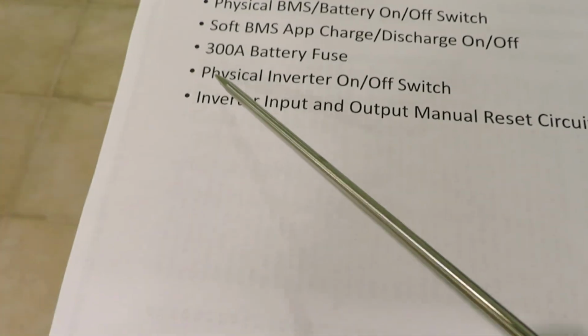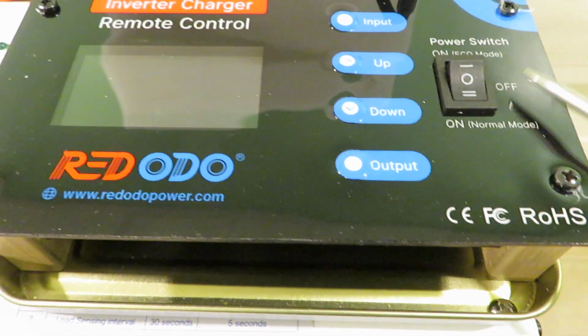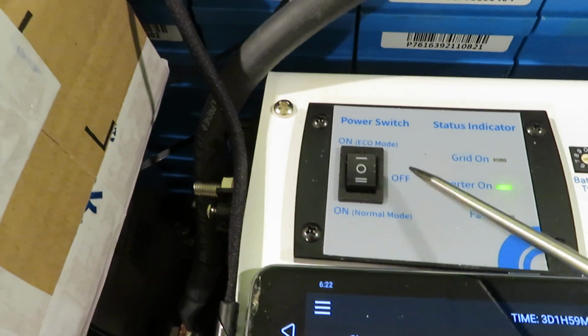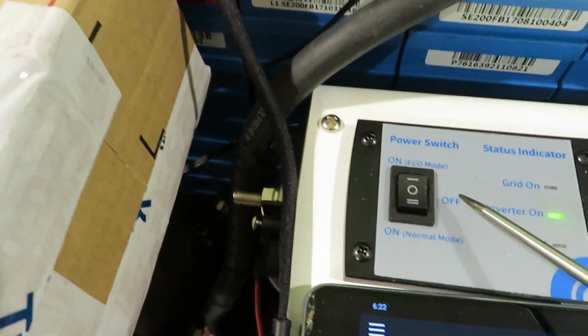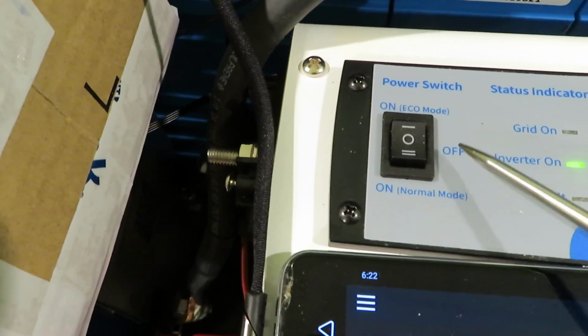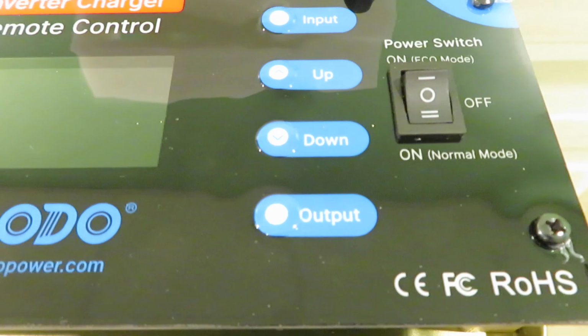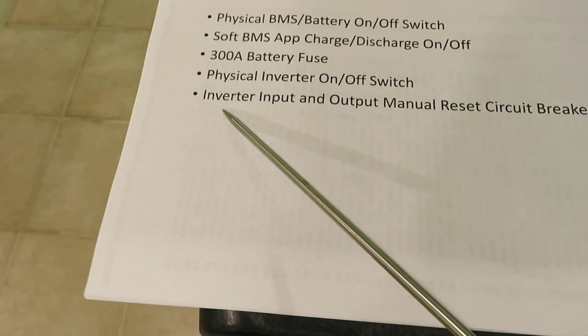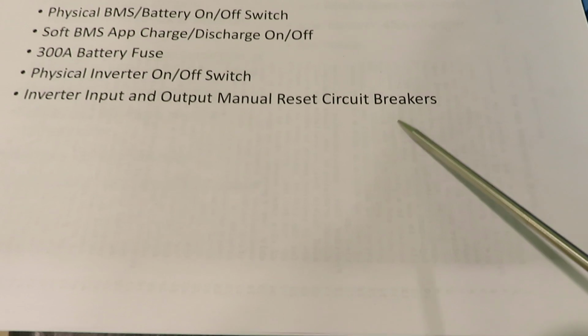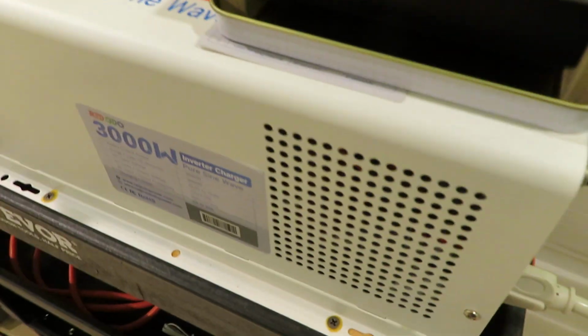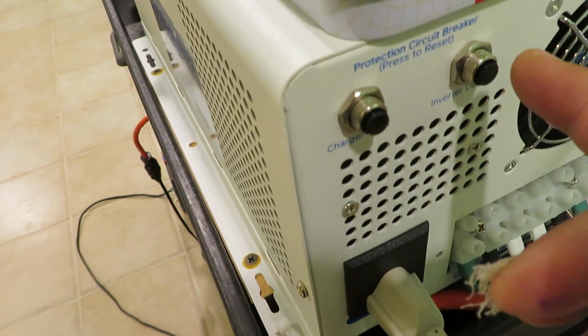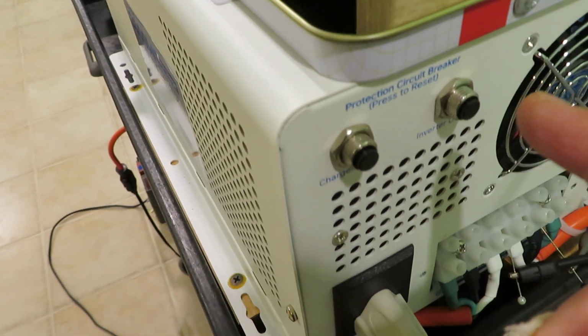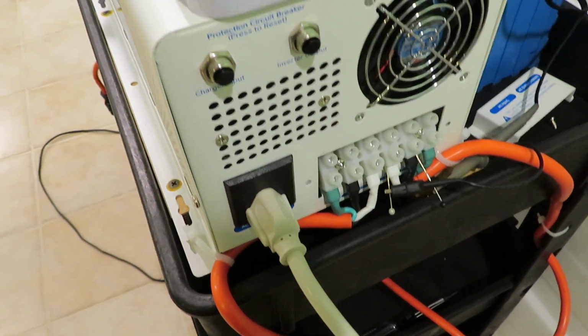There's also a physical inverter on-off switch, and this is the inverter remote on-off, which has priority over the physical switch on the inverter itself. So for it to work properly, the inverter's physical switch has to be set to off, and the remote switch used to turn the inverter on and off. Lastly, there's the inverter input and output manual reset circuit breaker—two circuit breakers for the input and output AC reset in case of overload or similar issues.